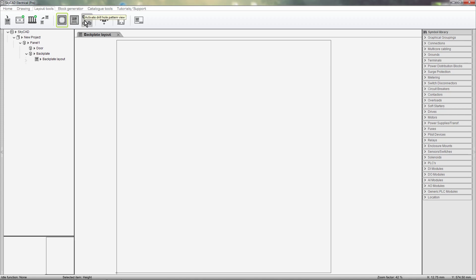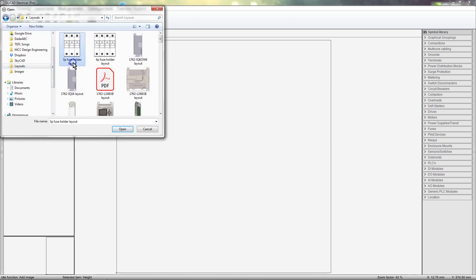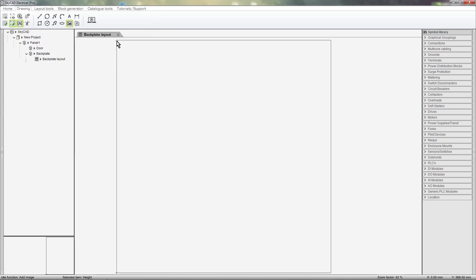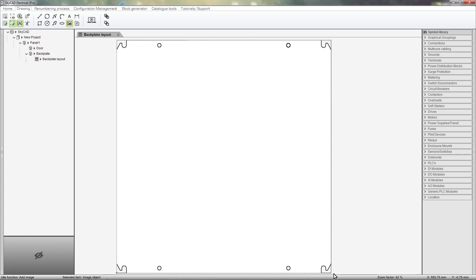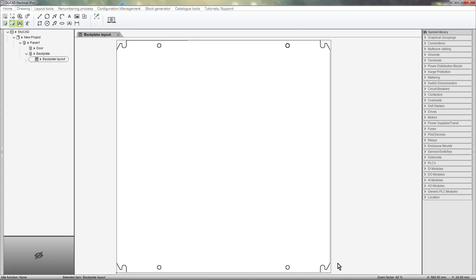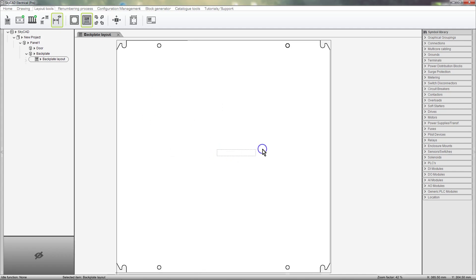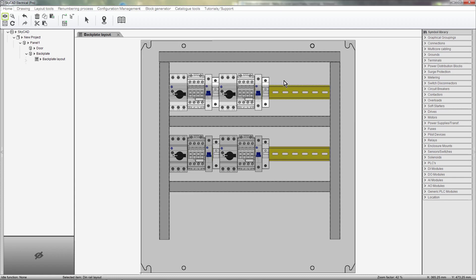The Drill Hole Pattern View is where cutouts and drill hole dimensions are shown — more about this view is covered in a separate tutorial. The Background View is used specifically for Location Layouts, which is what we are doing now. Whatever we insert in the Background View will not be in the way when working in the Main View. Let's insert our Backplate Layout image onto the Background View. If I activate the Main View once again, I cannot move or select the backplate, because the image is in the Background View. This is handy because you don't want to accidentally move your backplate when trying to insert components and DIN Rail onto your Panel Layout.